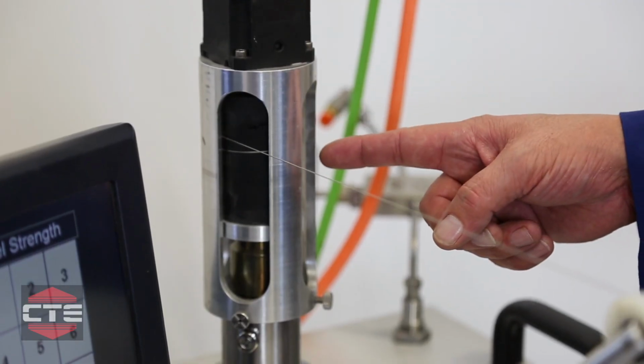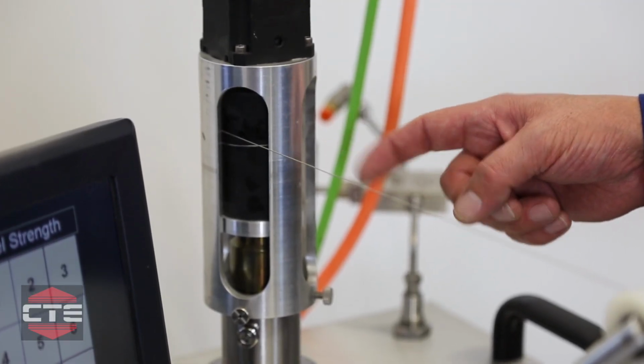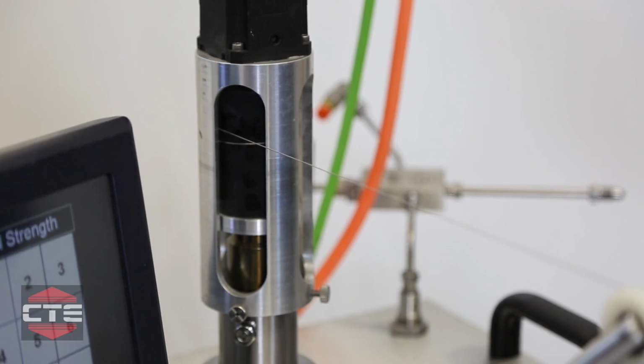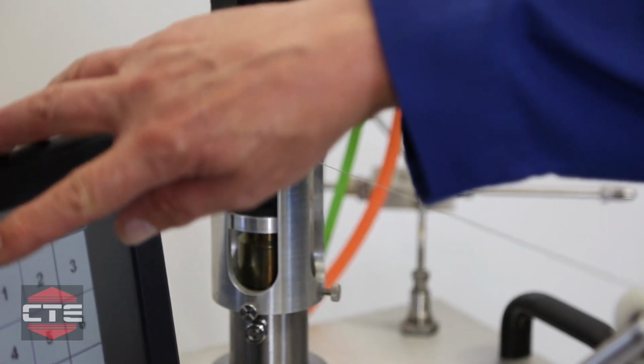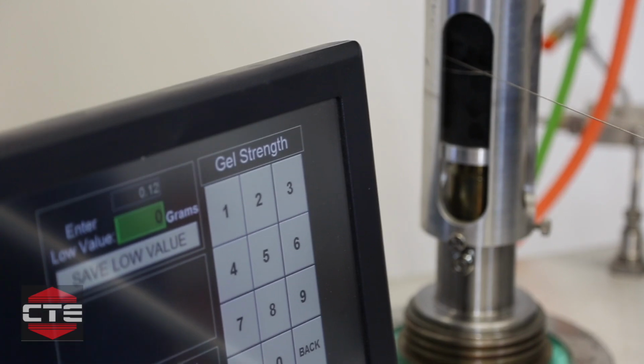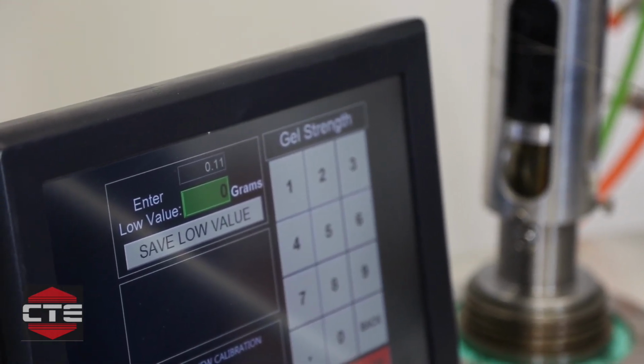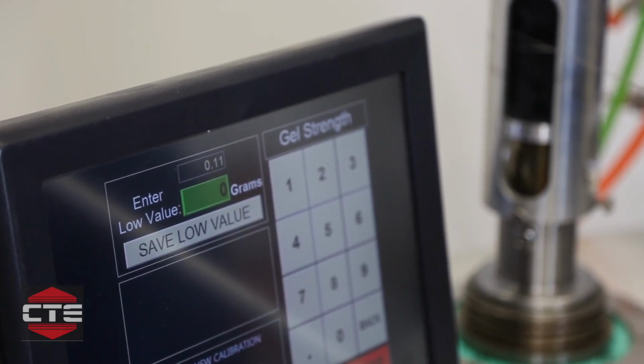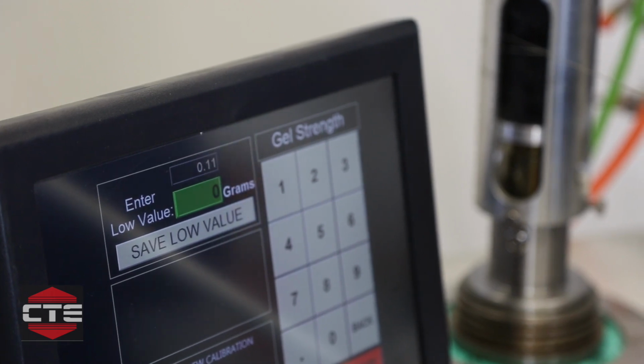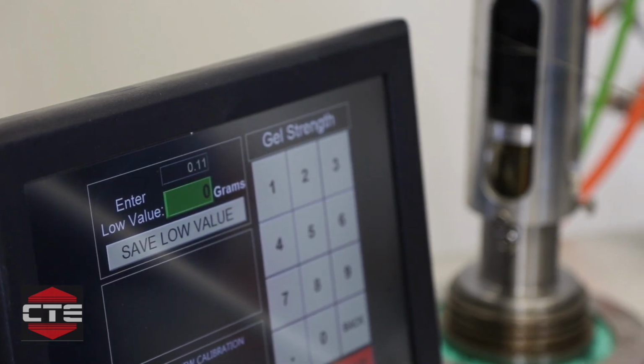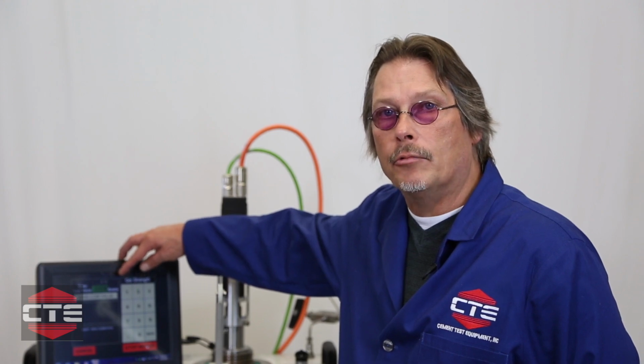As you can see, your motor is going to make 3/4 of a turn, and then it will stop and hold 100 grams. This is where you want to pay attention to your raw value. As you can see, it's fluctuating right now. The trick to the calibration of this instrument is the motor makes such tiny measurements that your raw value will fluctuate at some point. As you can see, it went from 0.11 to 0.12. The key to this calibration is letting your raw value settle out to one value. This could take up to 10 minutes for the motor to warm up and settle on one value.